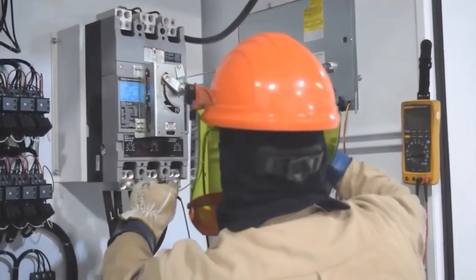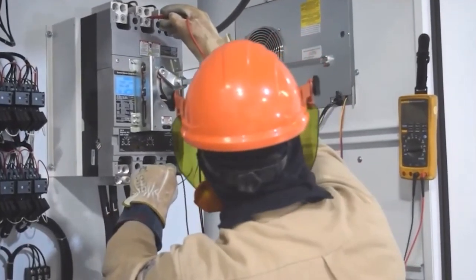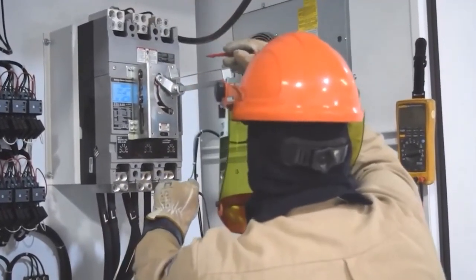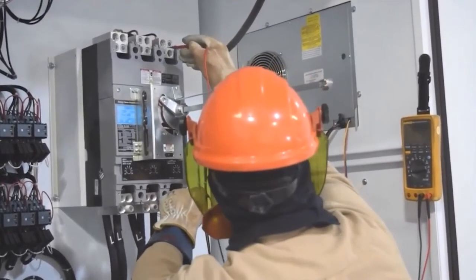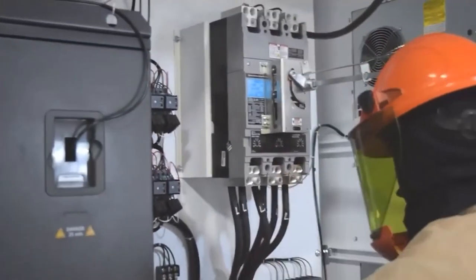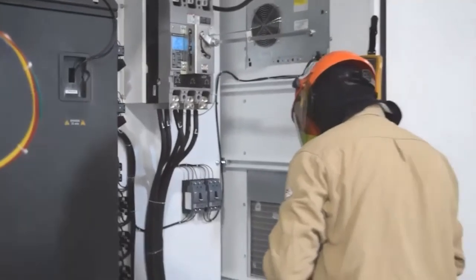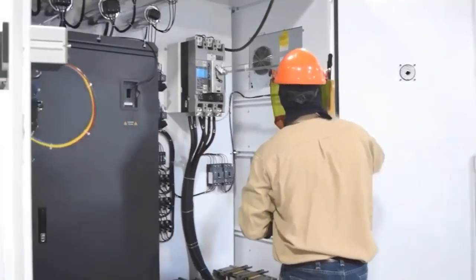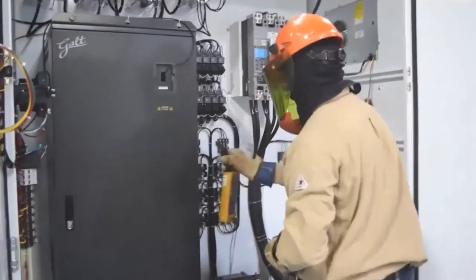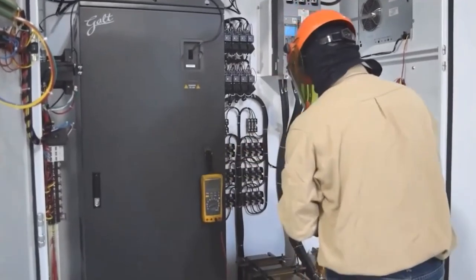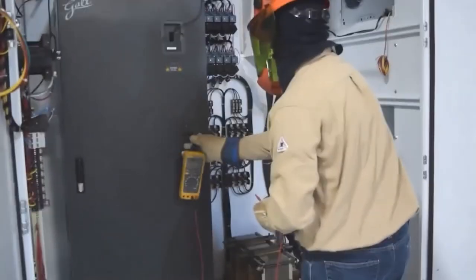And then I'm going to go ahead and measure on A phase, the top of the breaker to the bottom of the breaker. And what I'm looking for here is that I should see 0 volts. 0 volts is an indicator that all my points are good. If I measure a high resistance there, if I have a high resistance connection, I'm going to see some voltage across that.